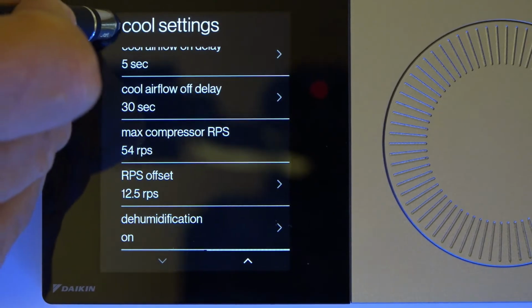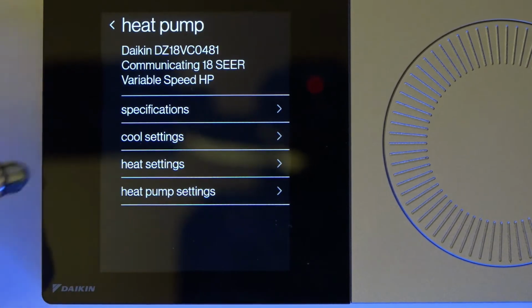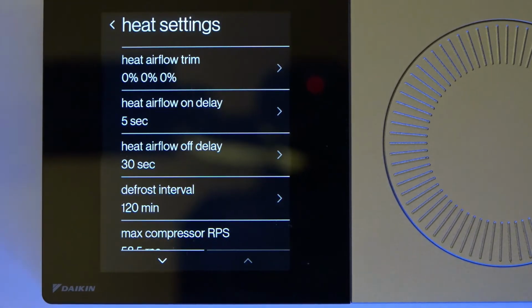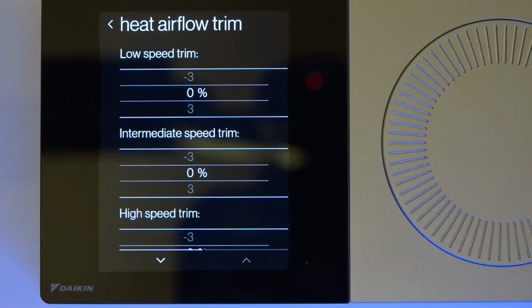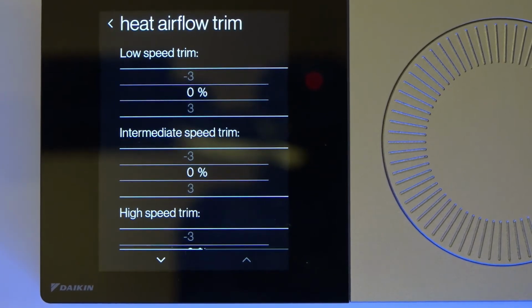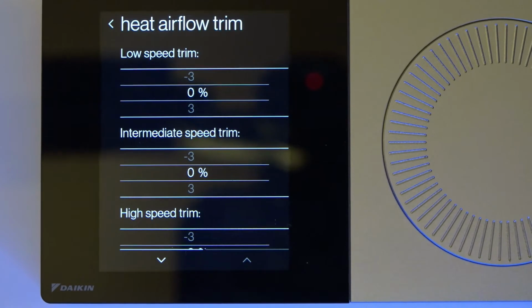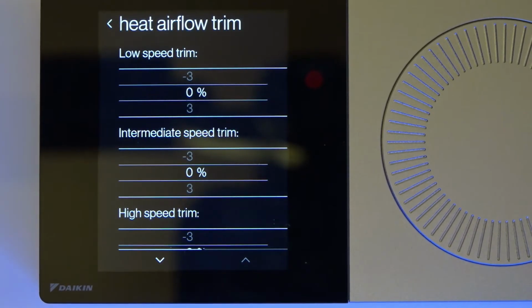So let's back out of cool settings. We can get into heat settings. And then I've got 3 more settings for a heat pump. So I got 3 for cooling and 3 for the heat pump. So now I can tweak these settings if I need to be able to get a certain type of temperature out the vent. I'm typically targeting 96 degrees or greater is what I want to see. Your skin temperature is roughly 86 degrees. Anything above 86 degrees is going to feel warm, and once we get above 96, 98 degrees, then it starts feeling really comfortable to us.